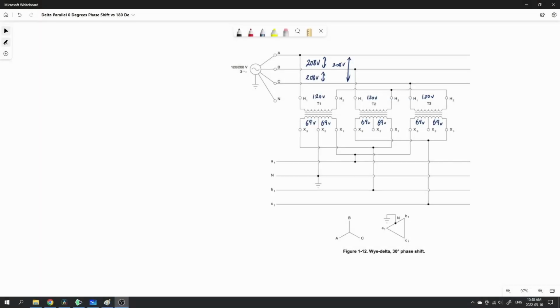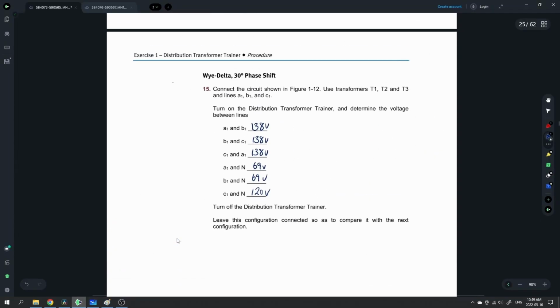Okay, let's see if we can figure out where that voltage was coming from, right? Because we were looking at our values here. So we had 138, that was obvious, between A and B, B and C, C and A. Then between A and neutral we had 69, B and neutral we had 69, and C and neutral we had 120. Let's see if we can figure out why C to neutral was 120.